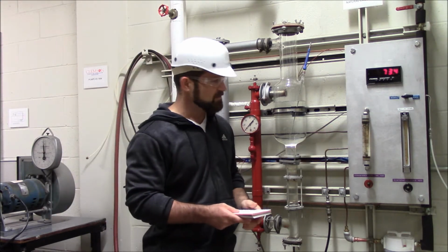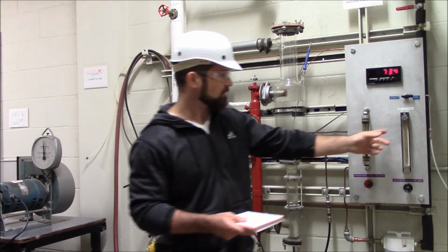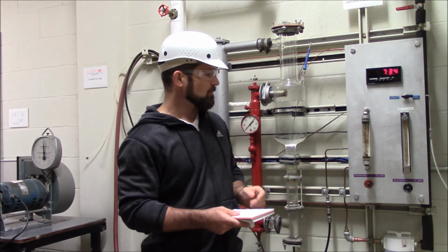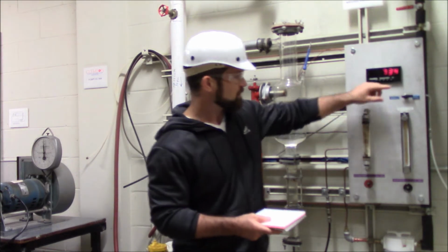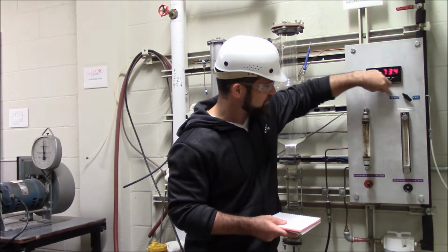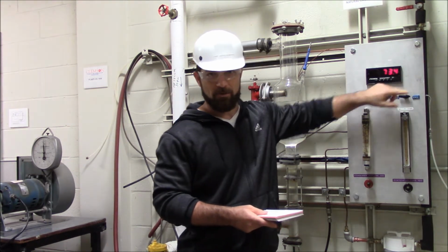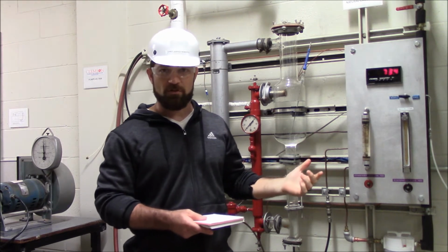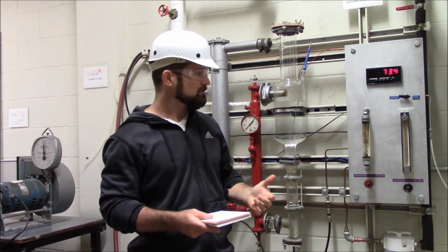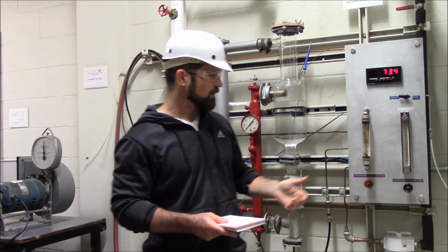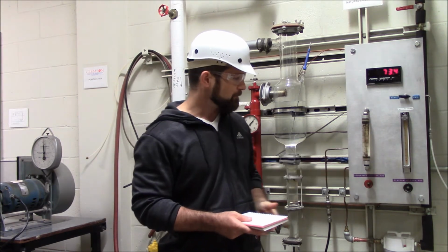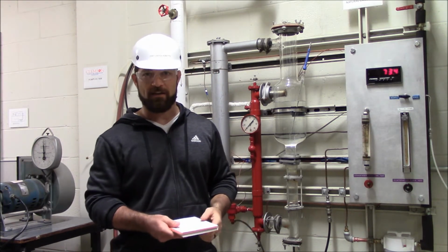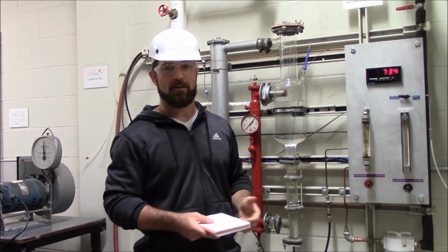Okay, the unit also has a couple of rotameters. The rotameter on the right is your rotameter for the evaporator feed. This also has a valve where you can switch between evaporator feed and calibration. So your procedure should include some instructions for either calibrating this rotameter or verifying the calibration curve that was provided, depending on what your assignment is.